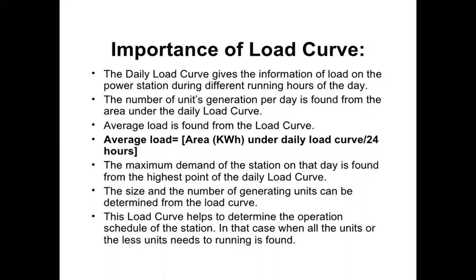First, we will discuss what is the importance of the load curve. The load curve will give an idea of the amount of energy consumed in a day. A daily load curve also gives an idea of defining running hours of a power station. The average load is the area under the daily load curve divided by 24 hours. From the load curve we can also find the maximum demand of the station. The load curve also gives us an idea about the size and number of generating units required, and helps determine the operation schedule of the station.